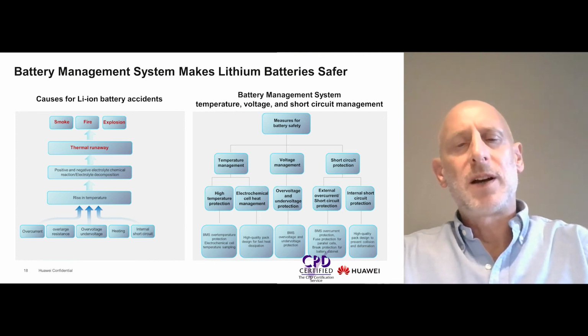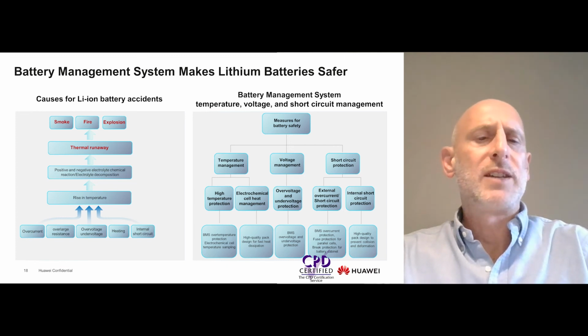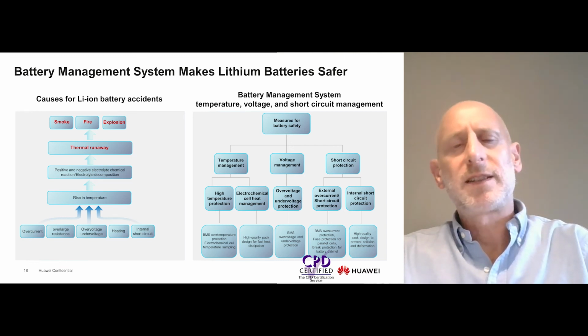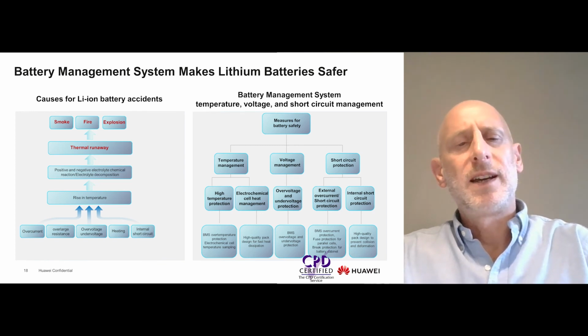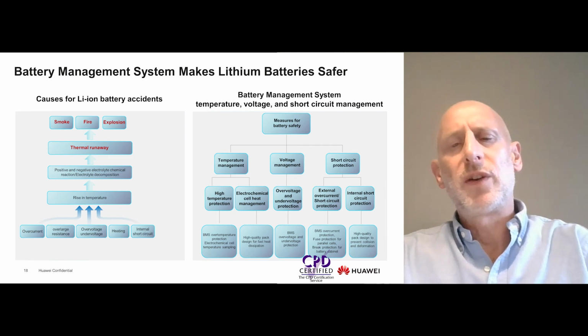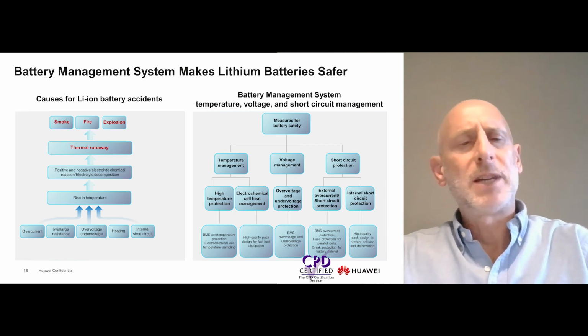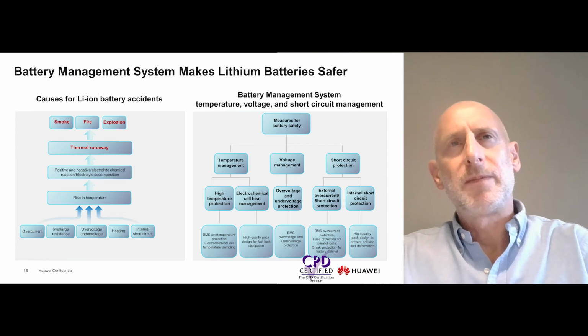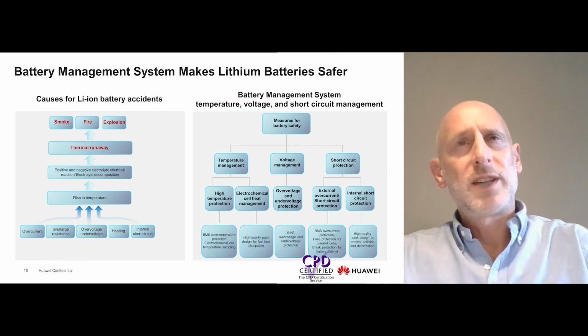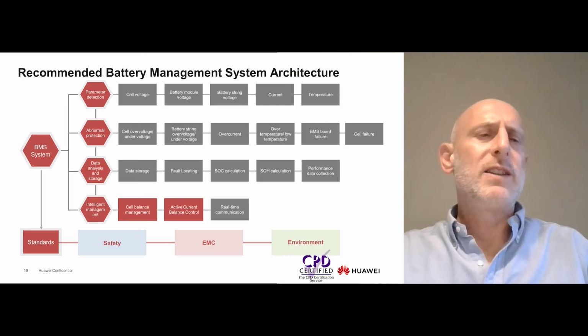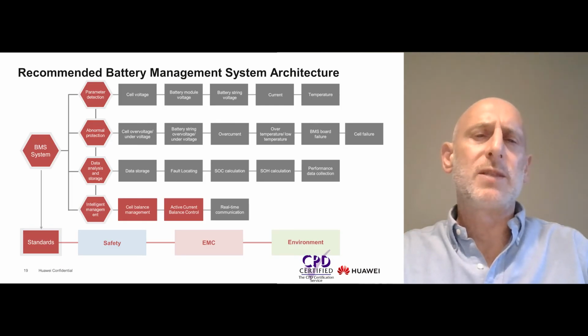Proper management system architecture is key to prevention. The system must be capable of monitoring cells, batteries, and racks. Protection measures must be taken to cope with abnormalities, and in case of overtemperature or overcurrent of cells, damaged batteries must be isolated in time to prevent fire. The important takeaway here is clear: appropriate management and containment of lithium-ion batteries maintains a safe and protected environment. The preventive measure is to have a well-structured management system for monitoring.